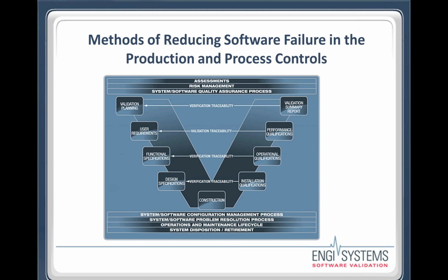The V-model approach can be used for the production software validation. Software in the automated production and quality control systems drive computerized equipment to perform desired tasks, plus operator manuals and instructions. The hardware system, software program, and general quality assurance system controls are essential to the automated manufacture of medical devices. The systematic validation of software and associated equipment will assure compliance with the quality system regulation, reduce cost, and improve quality.